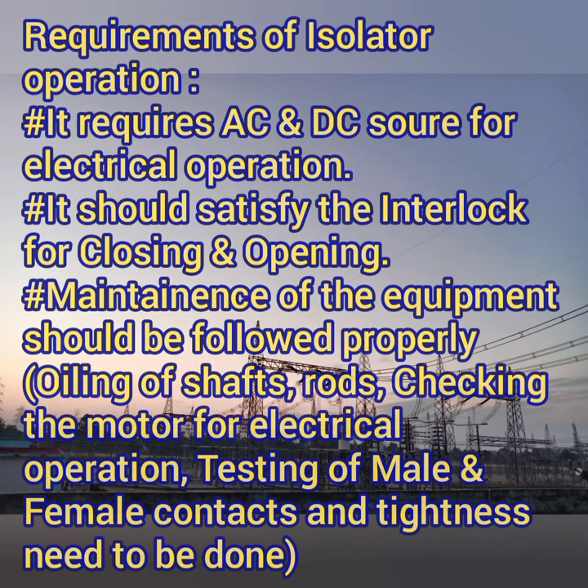For motorized operation, both AC and DC supply are needed — AC for the motor and DC for the control circuits, though this may vary by preference. The isolator must satisfy certain interlocks for both closing and opening. For closing, the breaker must be opened before closing the isolator. For opening, the breaker must be opened first and only then the isolator will open. These interlocks must be satisfied during operation.